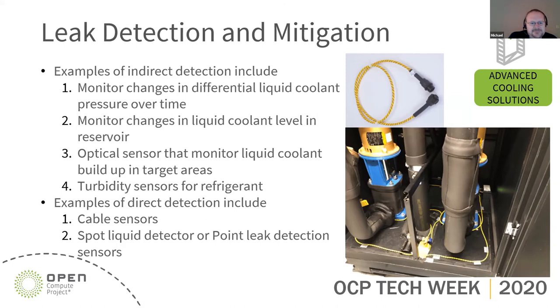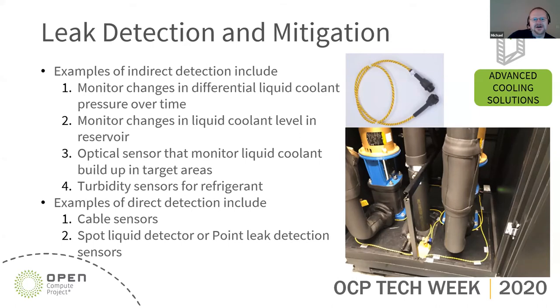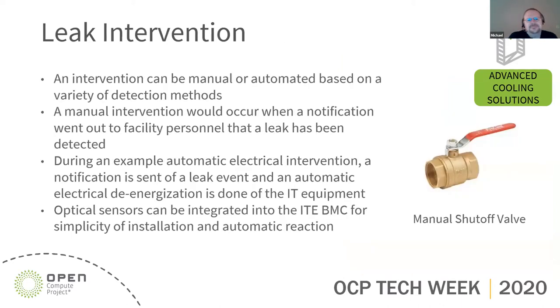For direct detection, we actually try to sense a pool of cooling fluid. Cable sensors can be placed around the bottom of a rack or CDU, especially routed where there are interfaces and points of failure — if there's a leak it'll drip down, touch the cable, and generate a signal. Similarly, a spot leak detector is handy where you have containment like a pan; at the lowest point in the pan you'd place a point leak detector. Cable sensors are one of the more common ways of detecting leaks.